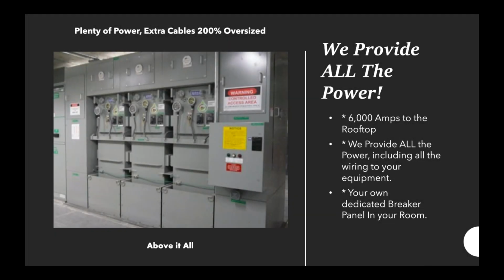As mentioned, we provide all the power to your transmitter room right up to your equipment, so you don't need an electrical or building permit. We're bringing 6,000 amps of power from the ground floor all the way up to the roof, with 4 wires involved in that.